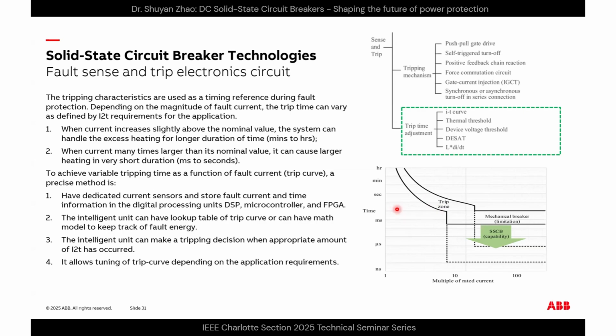So to achieve this variable tripping time as a function of fault current, which we see here as a trip curve, a precise method is to have dedicated current sensors and store fault current and time information in a digital processing unit: DSP, microcontroller, or FPGA. Those intelligent units can have a lookup table of the trip curve or have math models to keep track of the actual fault energy that it sees. And this unit can then make a trip decision when the appropriate amount of I squared T has occurred.